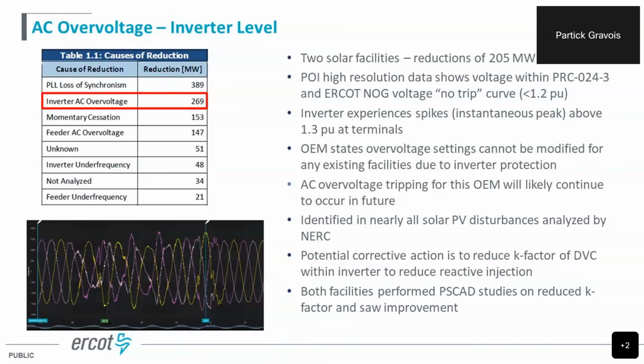From those real-time PMUs and PMU data sent in from these facilities, we didn't really see any voltages above 1.1 per unit during this event. But facilities were seeing inverter terminal voltage at 1.25 or 1.3 and tripping themselves off. The OEM, this is one particular OEM as well, for these 2 facilities, had stated that they cannot relax those thresholds for the overvoltage. It was needed for equipment protection.